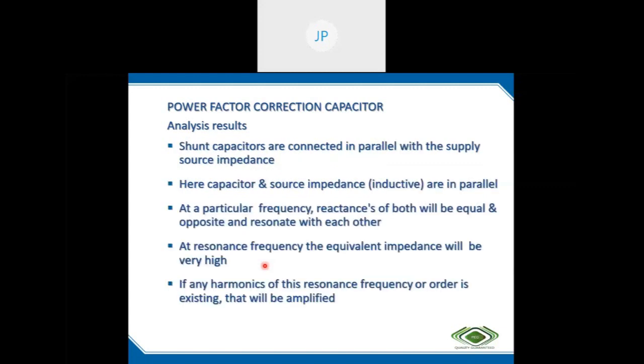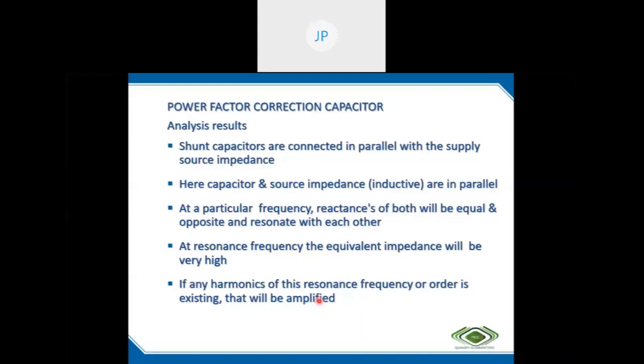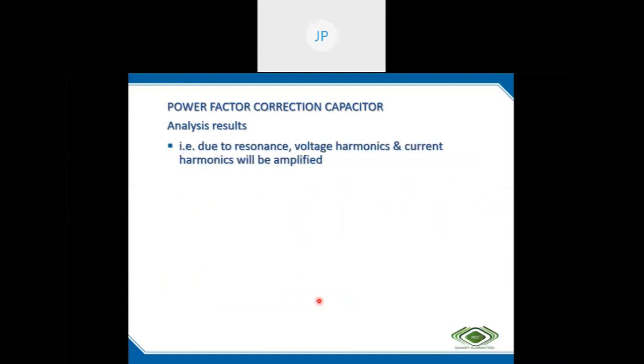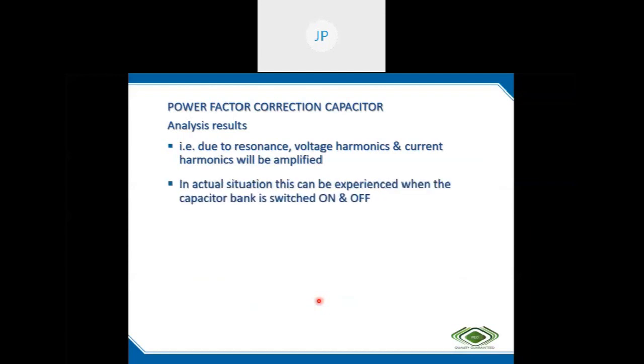For any harmonic of this resonance to be amplified, there should be something to amplify. If the fifth harmonic is 0, you cannot amplify it. So even though the resonating condition is there, if no harmonic of that order is present in the load current, nothing will happen. No amplification. So to amplify harmonics due to resonance, we need two conditions. One, there is a resonance condition in the system, and two, a harmonic of that frequency exists in the harmonic spectrum.